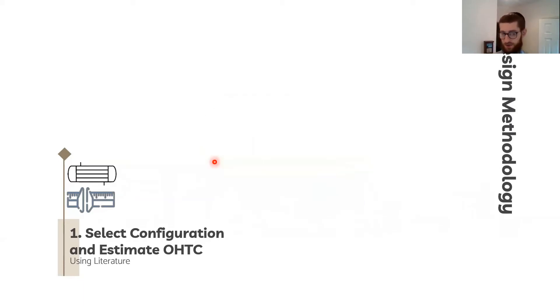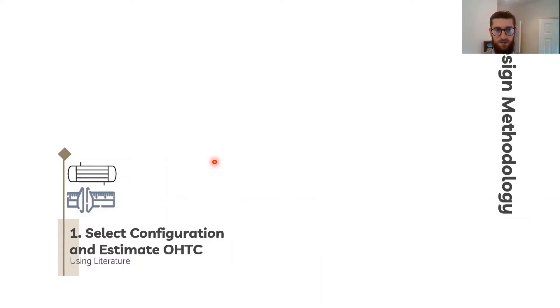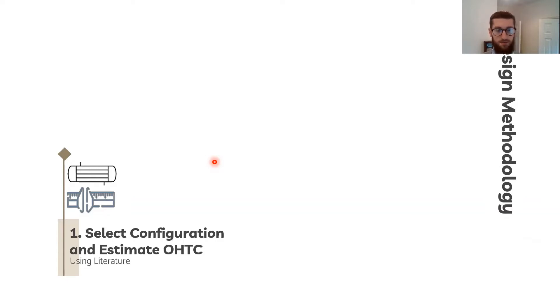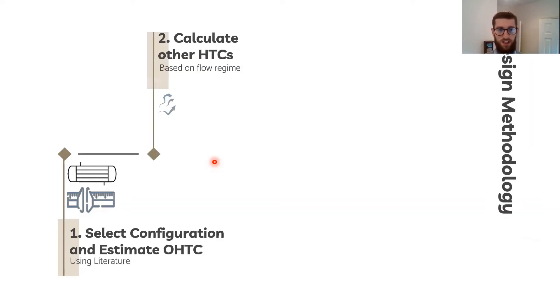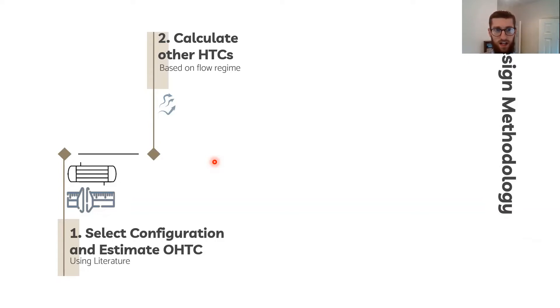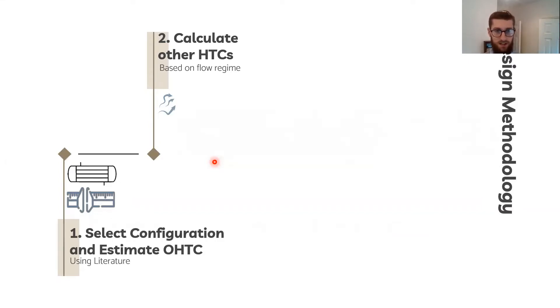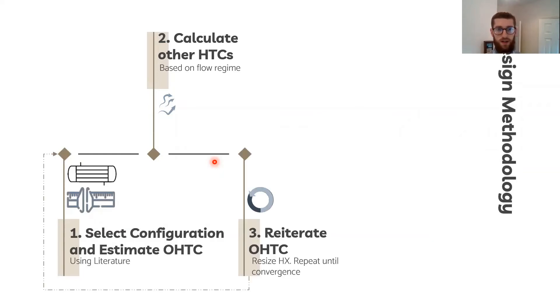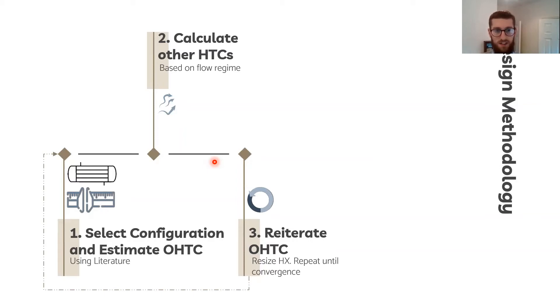Coulson and Richardson have a chart that is used for providing an initial estimate of the overall heat transfer coefficient, and that allows a rough sizing of the heat exchanger. With those sizes provided, the other heat transfer coefficients, internal and external, can be calculated based on that flow regime for that heat exchanger's size, and that provides the ability to create a much higher accuracy calculation of the overall heat transfer coefficient.